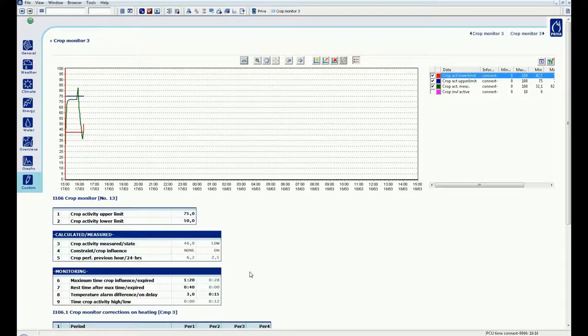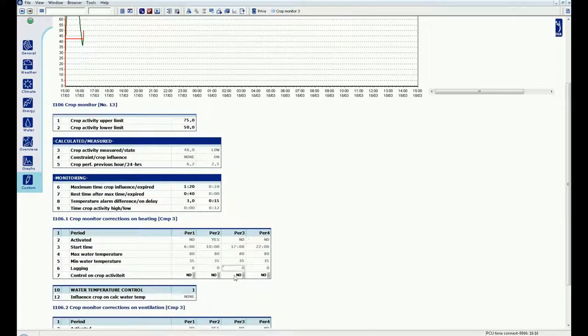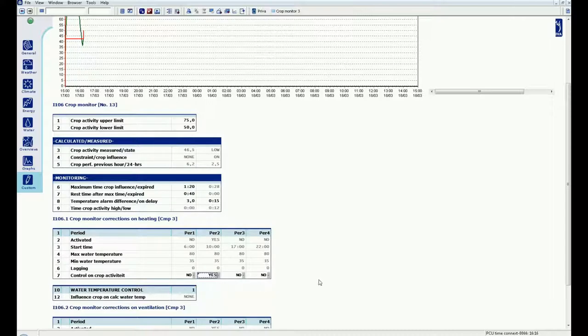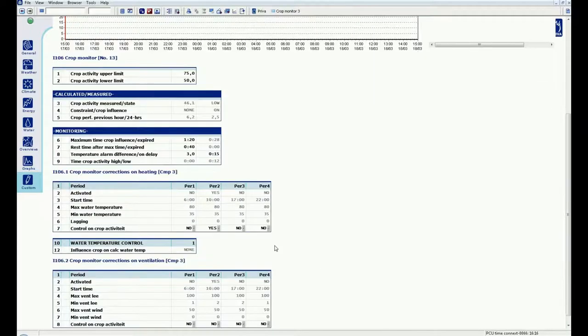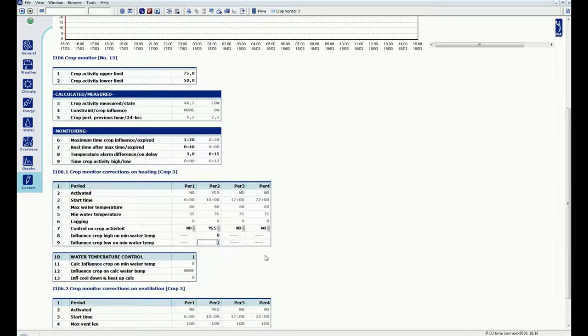Then I am going to set a crop influence on the minimum pipe in the second period. I change the control on crop activity to yes and there appears two additional rules. The influence at the high status and low status. I choose to raise the minimum pipe temperature with 15 degrees when the crop status is low. With the basic setting of 35, this means therefore a minimum pipe 50.